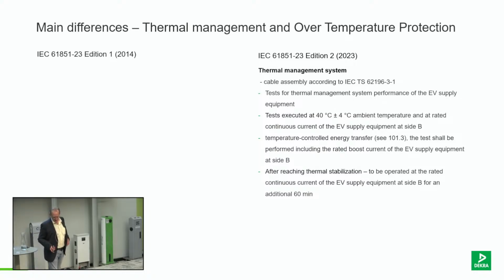That's over temperature protection. What is now also defined is that chargers have to be tested at 40 degrees centigrade with, let's say, the rated requirements, so at rated power and rated current. Also something which was not the case before.